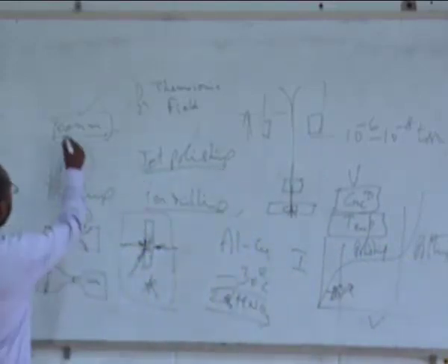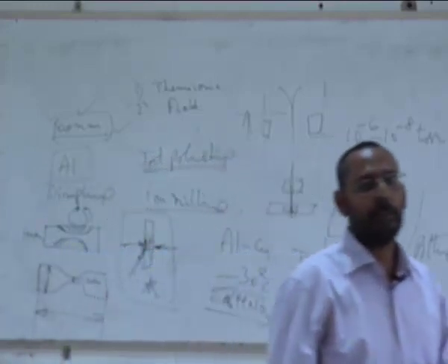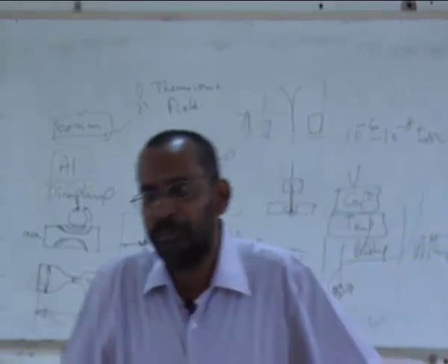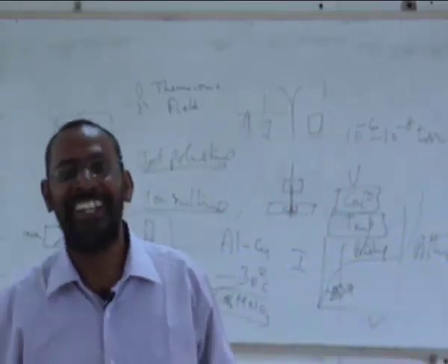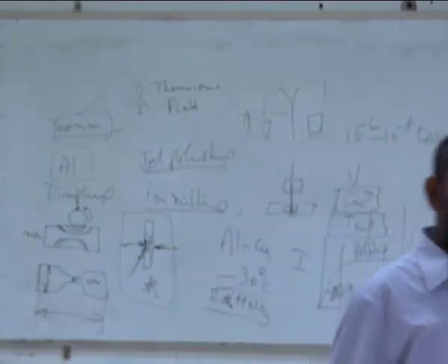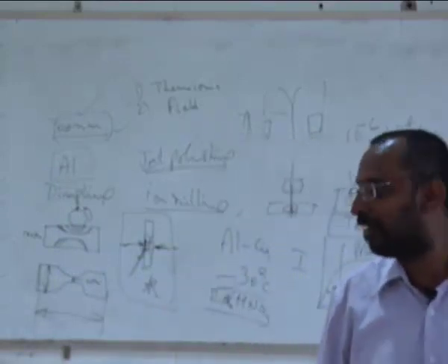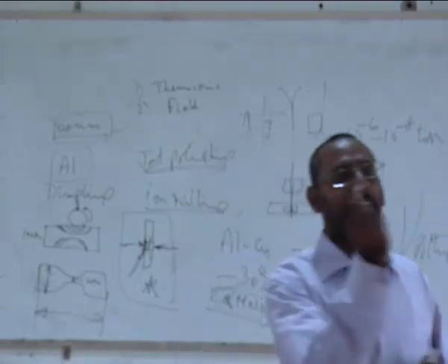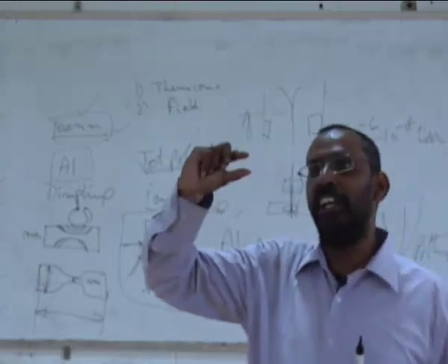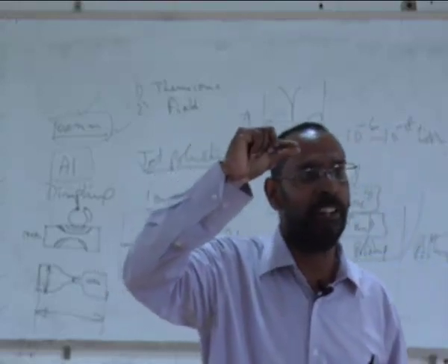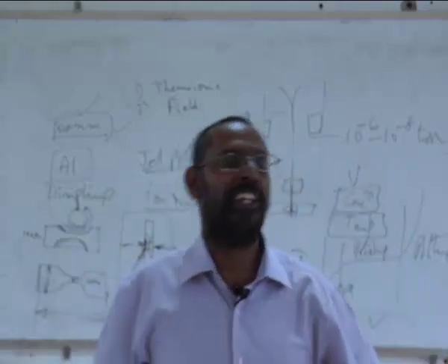The second aspect that you also need to know is not only the thickness, the diameter of the sample is also very important. In a TEM, the biggest sample that can go in is only 3 millimeters. Imagine what we are actually seeing: a sample which is 3 millimeters. Can you imagine 3 millimeters? So a 3 millimeter disc with a thickness of 100 microns starting, and finally finishing with 100 nanometers, is what I am actually seeing in TEM.